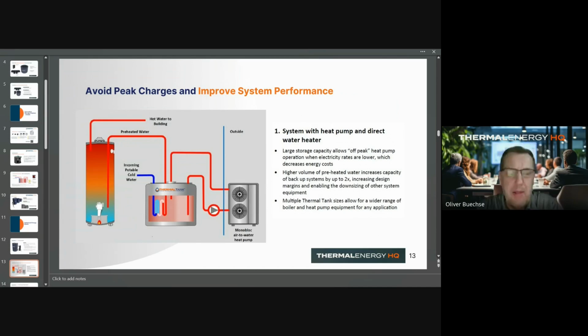And I recall we had a conversation with a very reputable engineering firm, and the lead engineer had brought up a drawing where he had 4 boilers and 4 heat pumps and a small buffer in between. And he immediately saw the opportunity by just expanding the storage. He could save at least one out of the 4 boilers and one or multiple of the heat pumps. So even the net system investment came down by inserting the thermal tank as a buffer storage there.